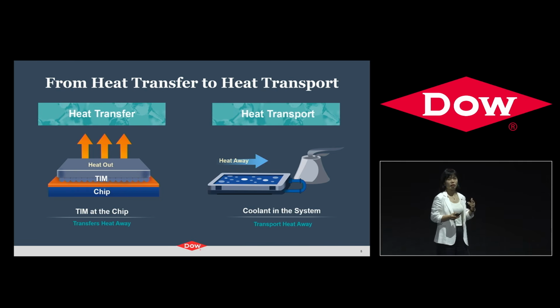The server generates a lot of heat. We need to remove the heat from the chip to the cooling hardware. That's what the thermal interface material team does. I will share more about that later. And then you need to remove that heat out of the system. That's what the coolant does for liquid cooling. So the coolant flows through the cold plate, absorbs heat, and carries the heat away to the heat exchanger or facility loop. So TIMs and coolant work together as two critical materials to help with the system cooling process.